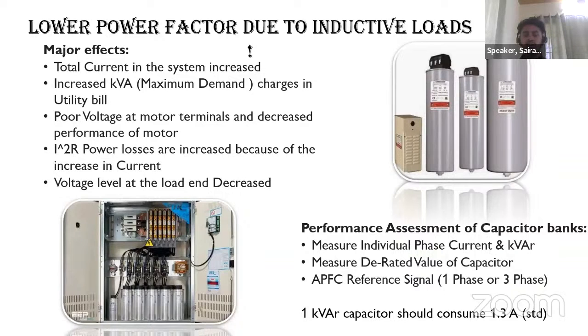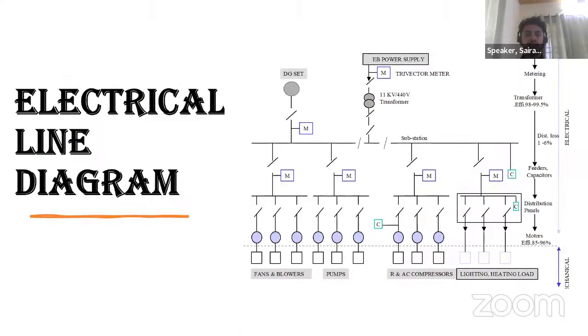Then for a 1 kVAR capacitor bank, it will be consuming almost 1.3 amps. It's a kind of thumb rule that we check during the measurement of the performance of capacitor banks.